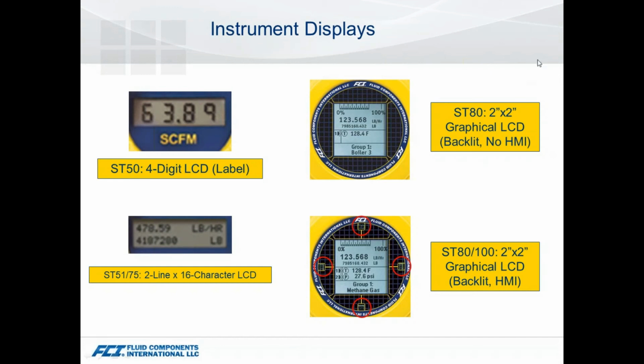For the newer released ST80, we have just a nice display. For an upgrade, as well as on the ST100, you have the option of touch buttons, so you have the ability to do a little configuration and access information in the field. When you look at that display, there's a lot of information here: a graphical representation of percentage of flow, flow rate, and total flow. You always also get the temperature reading.